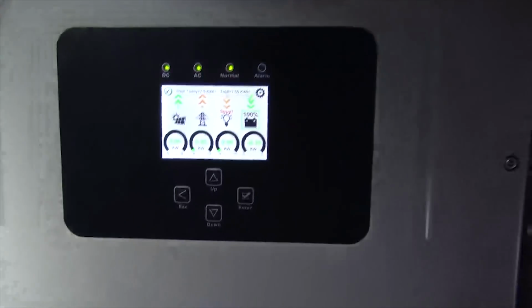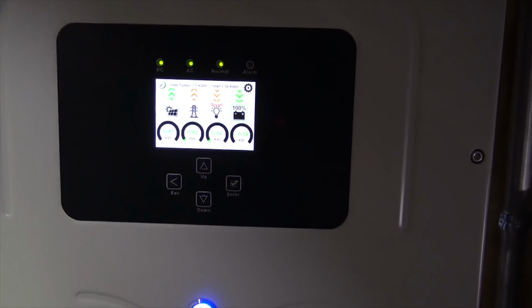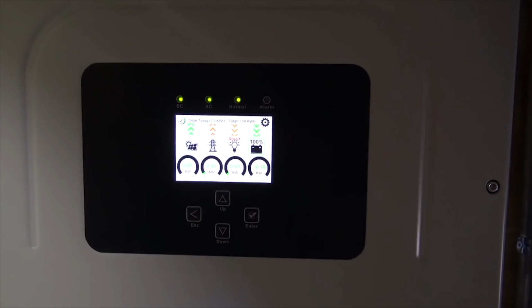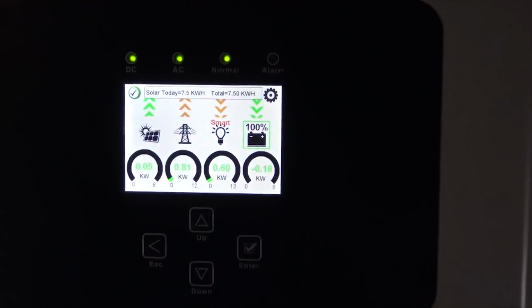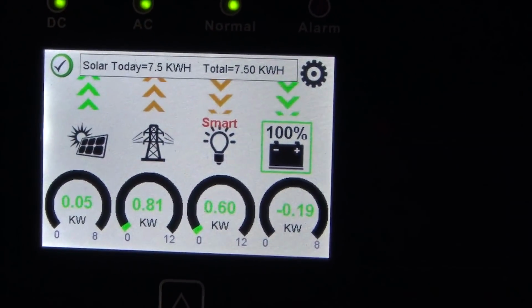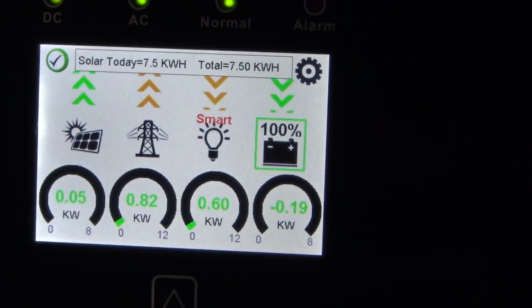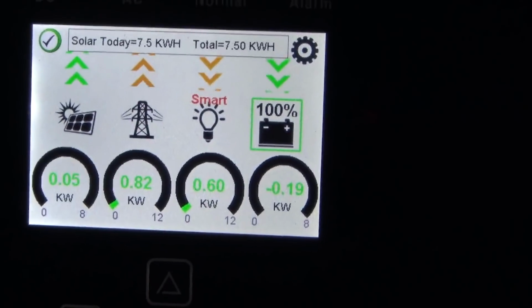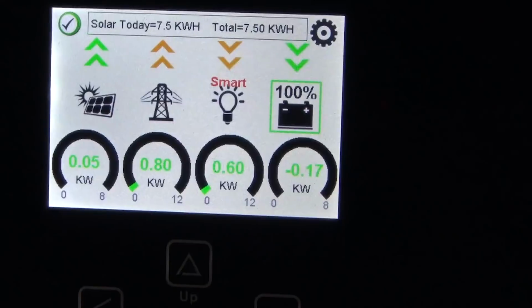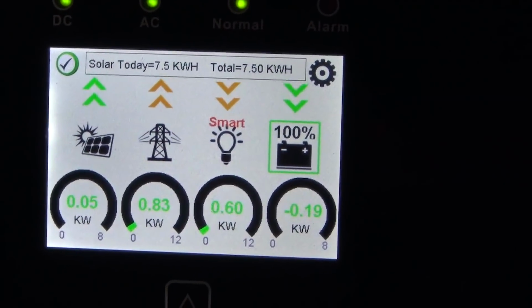Well, Tom over at Sol-Ark's been asking us to use this feature. This is the first installation where we're really using it. Actually, not true. I have one on the Canadian border where we're using it as well. So we're using the smart load as a way to heat the water in an electric water heater.